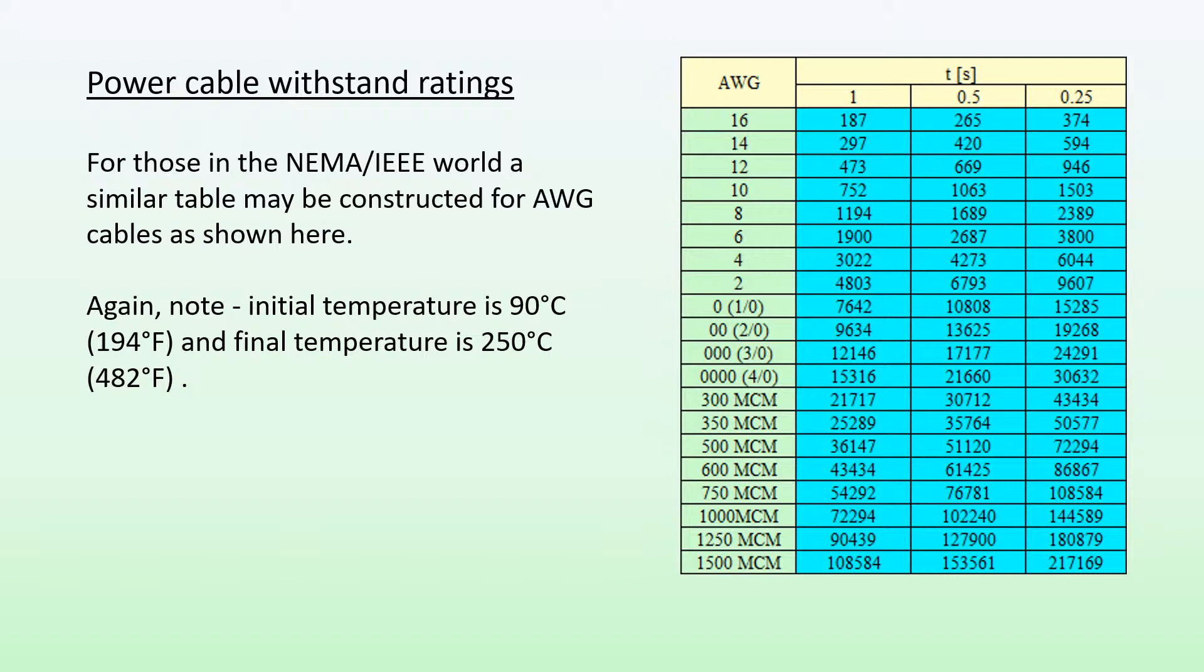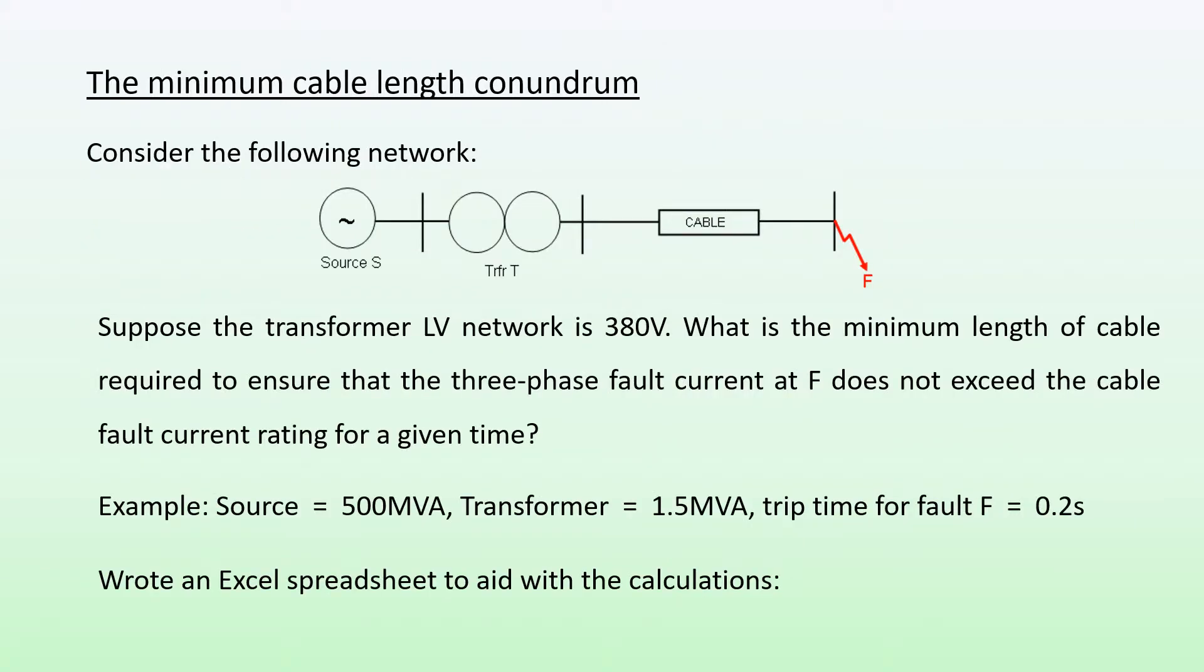So the minimum cable length conundrum. Let's consider the following network: I have a source, transformer, and a cable with a fault F at the end of my cable. Suppose the transformer network is 380 volts. The question is: what is the minimum length of cable required to ensure that the three-phase fault current at F does not exceed the cable fault current rating for a given time?